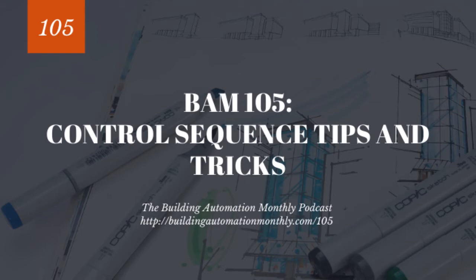Now you're thinking to yourself, well, I need to enable the air handler, so I'm going to move that above those VAV boxes. Well, therein can become an issue, and that would cause a major problem if you turn on an air handler and all of the boxes are closed. Sure, you'll trip the high static, but it's still a pain to have to go up and manually reset the high static, which is another side note: don't use automatic resets on high statics and low statics. But that's neither here nor there. That's a question I got in a forum just the other day, and I wanted to throw that out there.